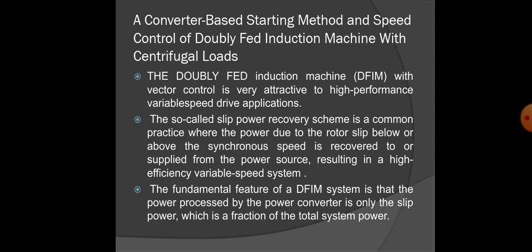The so-called slip power recovery scheme is a common practice, where the power due to the rotor slip below or above the synchronous speed is recovered to or supplied from the power source, resulting in a high efficiency variable speed system. The fundamental feature of the double fed induction machine system is that the power processed by the power converter is only the slip power, which is a fraction of the total system power.